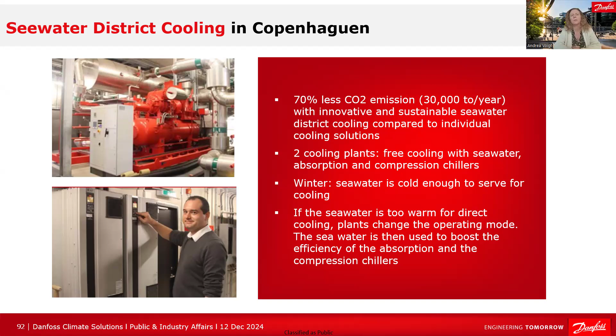Here in this particular case in Copenhagen, we have two distinct cooling plants. One is what I just showed, the free cooling with seawater. The other is a combination of absorption and compression chillers. That comes into play when the seawater isn't cold enough to provide district cooling directly. In that case, the plants change how they operate, combining absorption and compression chillers to bring the efficiency to the required level and cool the seawater as needed.